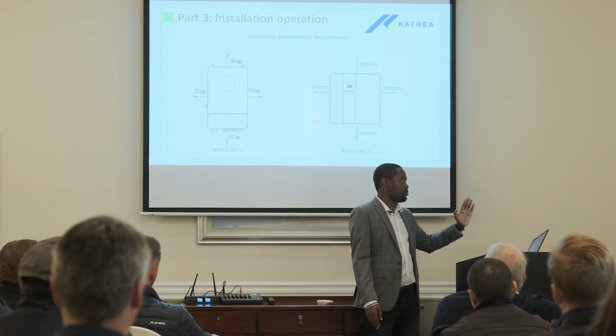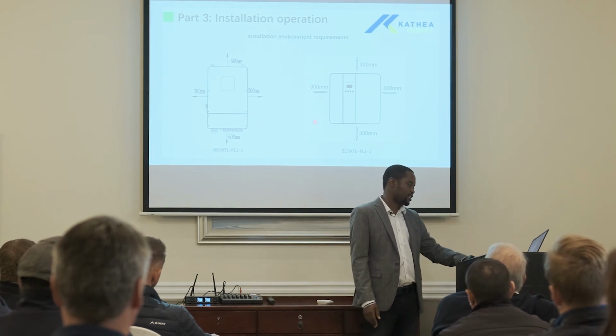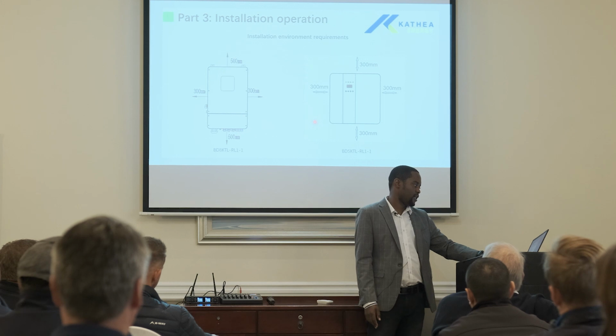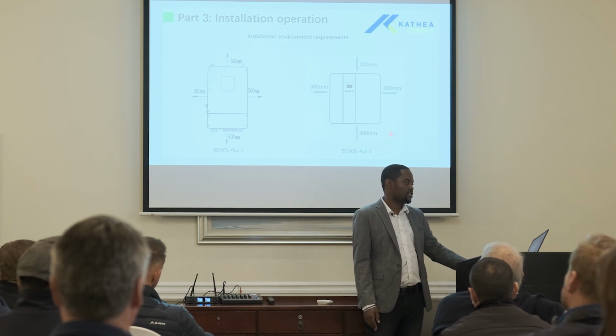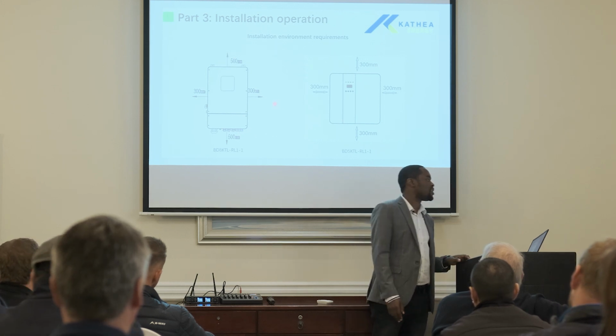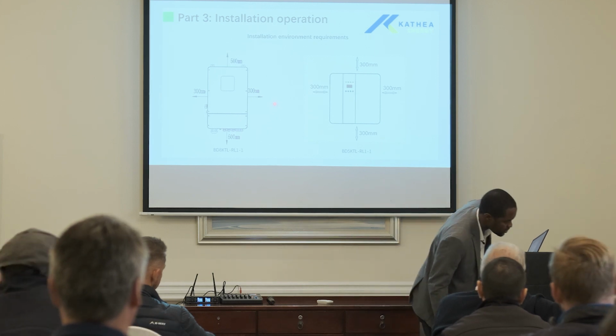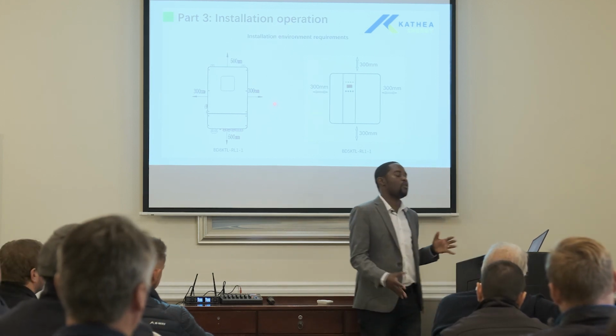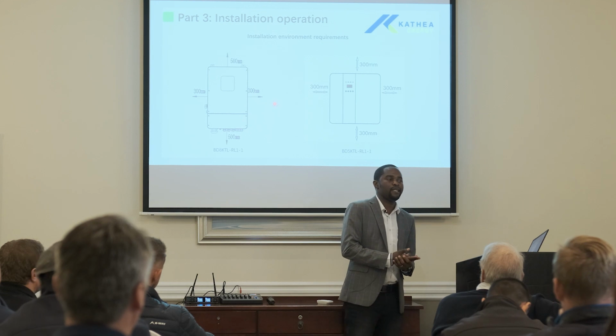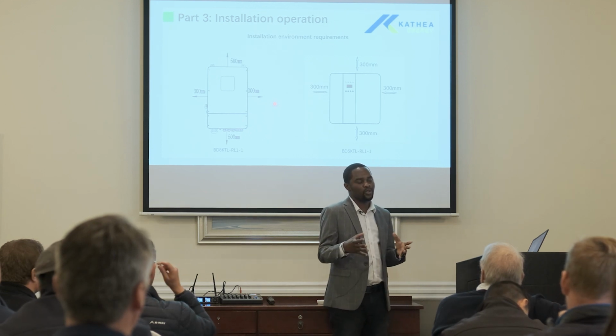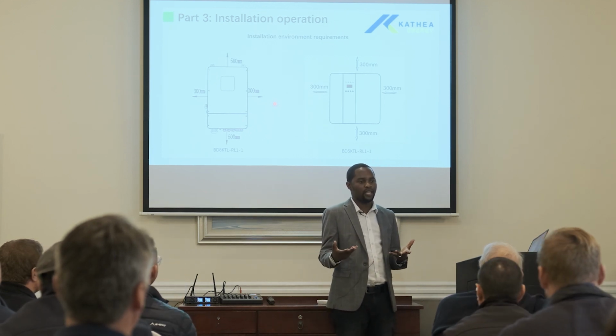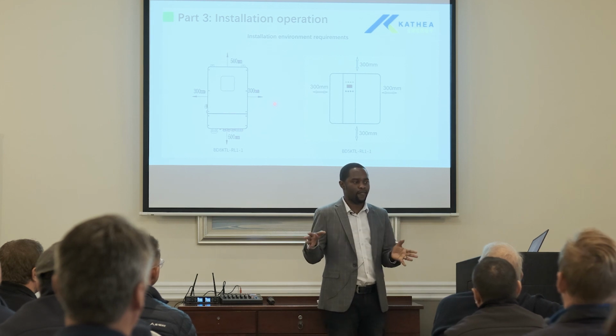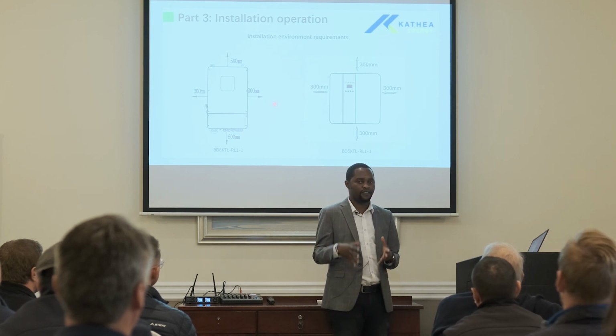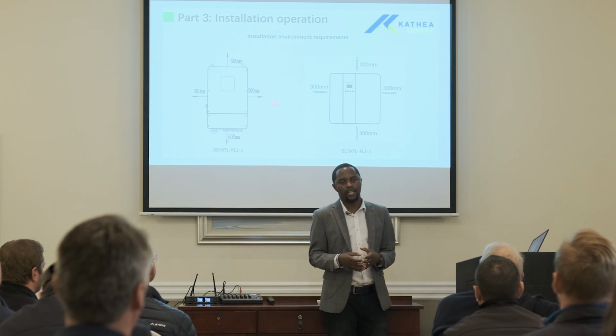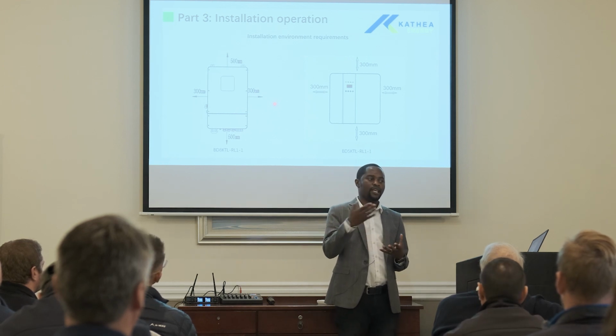Sense? Or we can put it close to the wall as long as you leave 300 millimeters from there. Then the 5 kilowatt, the 8 kilowatt, as you can see, I'm not sure if it's visible from this side. The fans are on the other side. So all of them use heat sinks for cooling. Then the 5 kilowatt is smaller, it does less work, so the heat sinks are actually enough. You don't have any running fans on the 5 kilowatt. Then on the 8 kilowatt, you've got heat sinks and you've got extra fans.